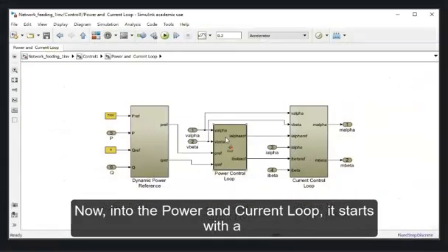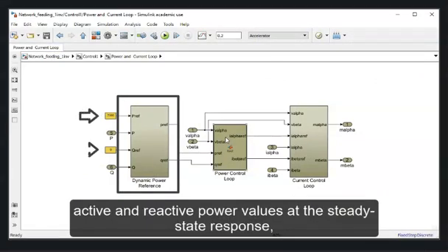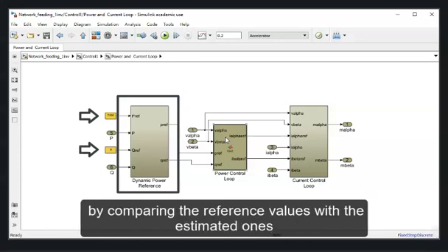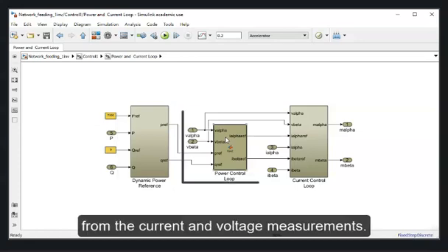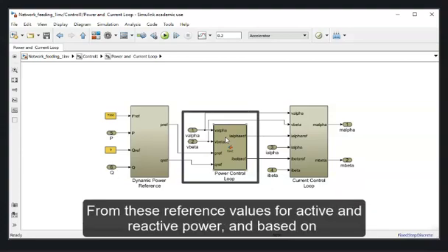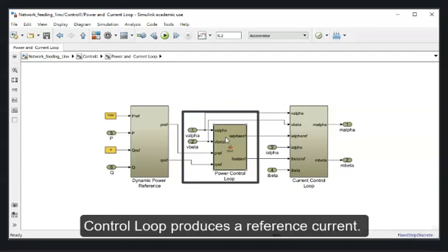Now, into the power and current loop. It starts with a dynamic power reference block, which ensures the specified active and reactive power values at the steady state response, by comparing the reference values with the estimated ones from the current and voltage measurements. From these reference values for active and reactive power, and based on the converter output voltage in alpha and beta, the power control loop produces a reference current.